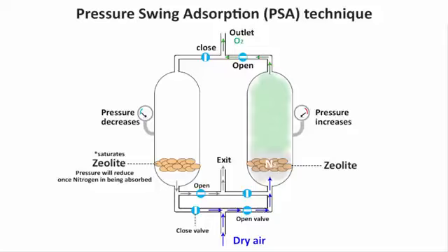Now this entire cycle is controlled electronically in such a way that when the pressure of the first tank goes down, the pressure of the second tank will be up, and vice versa. This process guarantees a continuous flow of oxygen. You don't have to wait for one tank to become empty and then start the whole cycle again. This cycle is then repeated under an electronic control system in order to produce high purity and stable oxygen continuously.